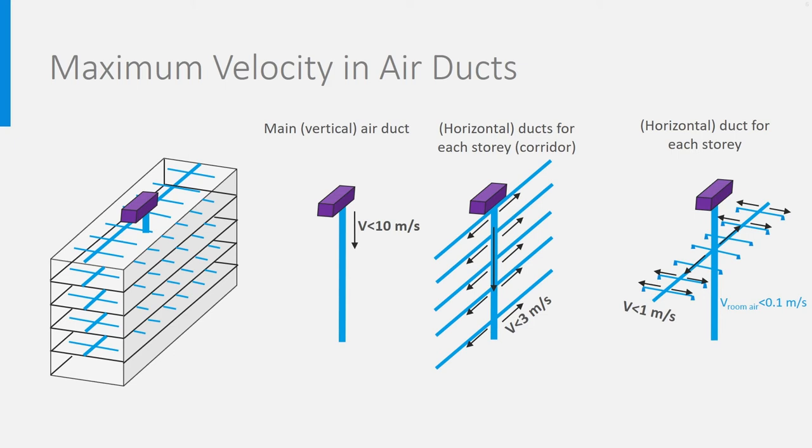How to size ducts? Next to the volume flow rates of air to be transported, we need to account for the velocity of the air flows. The higher the velocity, the more noise and resonance will be produced by the air in the ducts. And, as you may have learned in another course, noise is an important parameter of indoor environmental quality. Additionally, the higher the velocity, the higher the pressure losses. When the pressure losses are high, the power of the fan increases, causing more energy use.